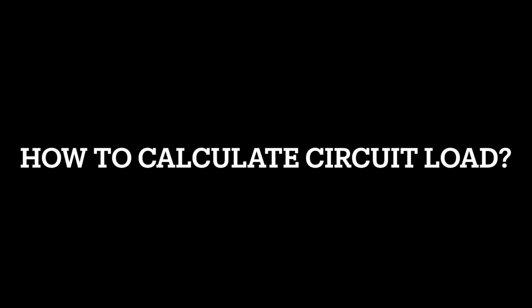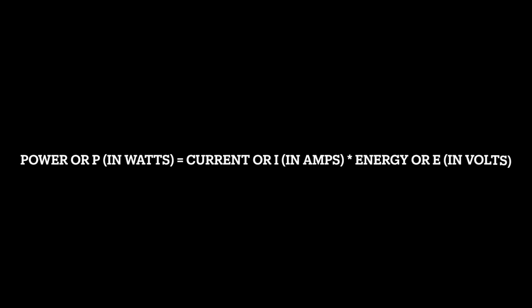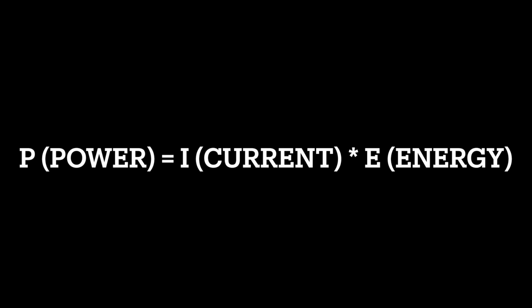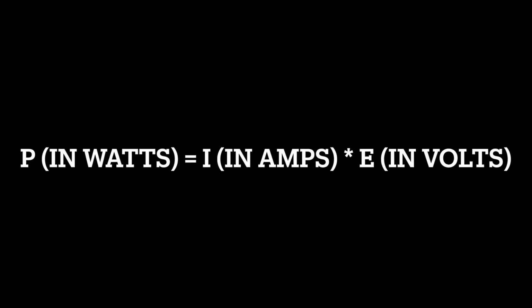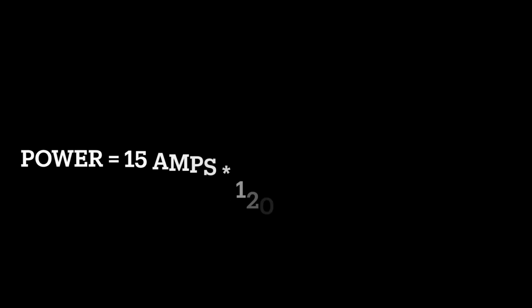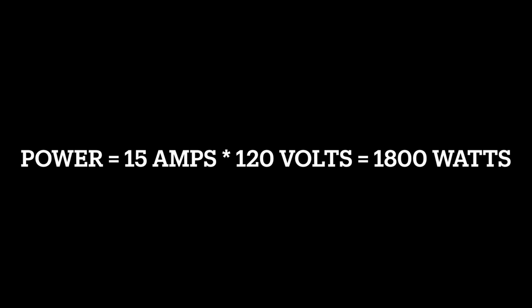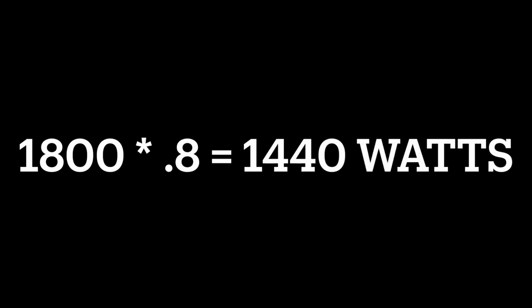If you've completed high school, you might remember physics class where we learned the formula power, or P, in watts equals current, or I, in amps, times energy, or E, in volts. P equals I times E. All homes in North America support 120 volts for small load circuits like 15 amps, where 15 amps is the current. We plug these values into our equation and we get power equals 15 amps times 120 volts equals 1800 watts. Remember what I said earlier? We should think about provisioning just 80% of this capacity, or 1800 times 0.8 equals 1440 watts, which is equivalent to 12 amps on a 15 amp circuit.